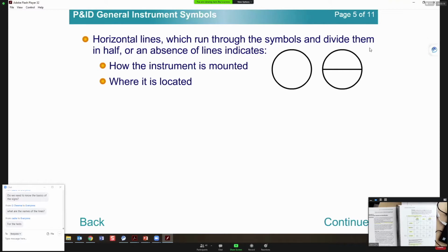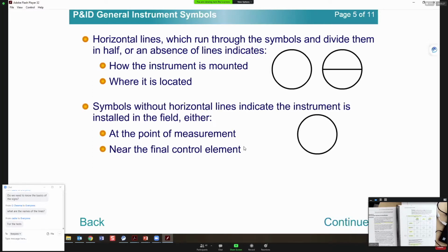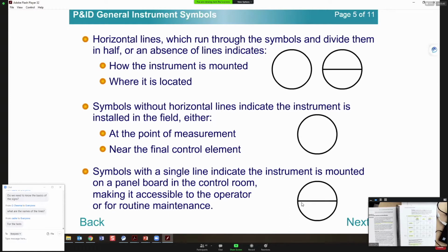A horizontal line runs through the symbol. It will tell you how the instrument is mounted or where it is located. If there's no line in the center, this device or equipment is mounted at the point of measurement, or it's near the final control element. If you have a single line in between, that means this instrument is mounted at the panel board in the control room. So it's accessible to the operator. It's usually in the control room for the operator, easy to get access to.